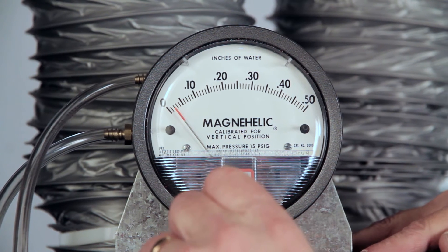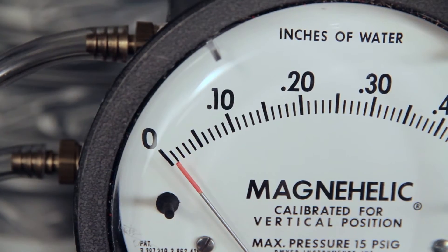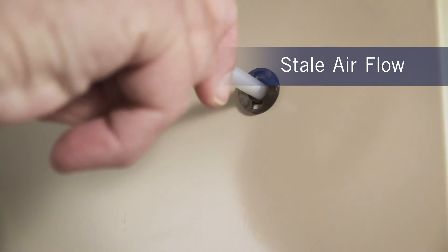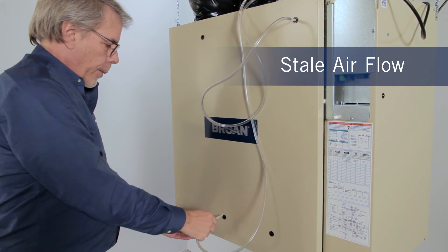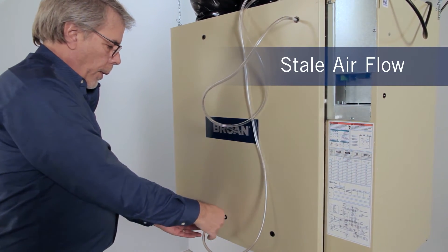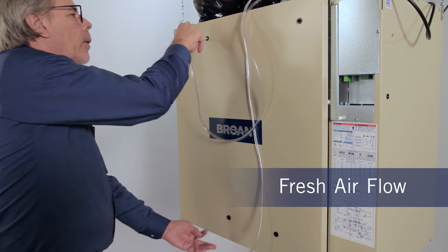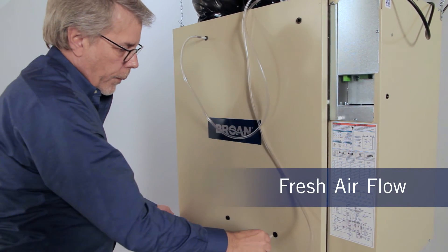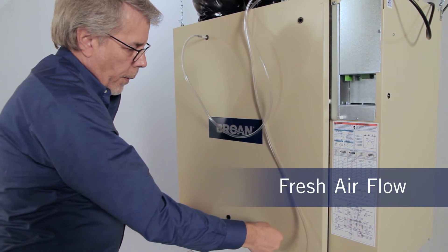Place the pressure gauge on a level surface and adjust it to zero. According to the airflow to be measured, connect tubing from gauge to stale airflow or the fresh airflow pressure tap. Be sure to connect the tubes to their appropriate high-low fittings. If the gauge drops below zero, reverse the tubing connections.